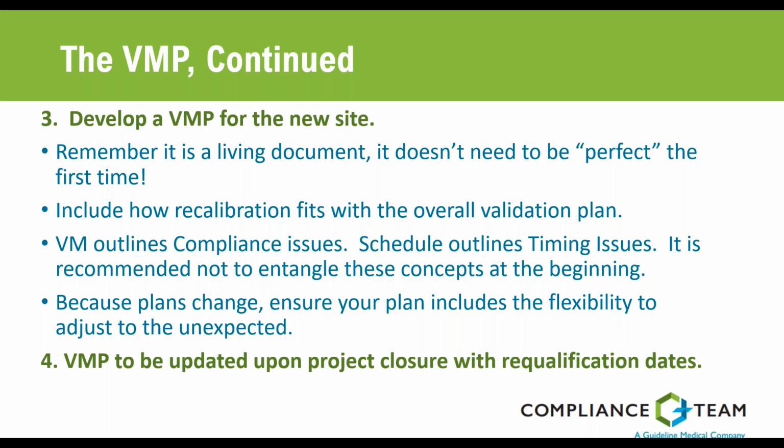The other thing you might want to consider is recalibrations. Is recalibration potentially sufficient to establish that your equipment is suitable in its new location? It might be, but that needs to be discussed through risk assessment, and we'll get into that later.